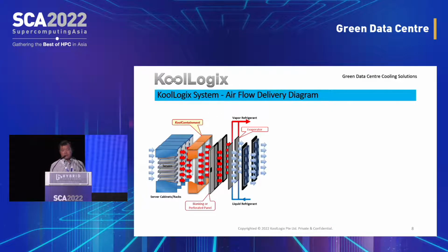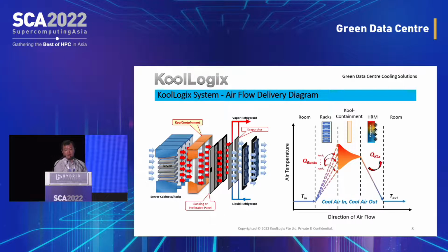Okay, so looking briefly a bit more into what's happening in the airflow, I have shown multiple racks in a row. Same thing: the cool room air goes in, picks up the heat, goes through the cool containment, and goes through the evaporator, and so on. If we track the air temperature from left to right, in the direction of the airflow, the air goes in at the cool temperature T in, and the temperature rises through the servers. The key point I want to highlight is that different racks can dissipate different power. Yet the cool containment has the ability to mix this flow and distribute it into the HRM, and the HRM removes the heat.